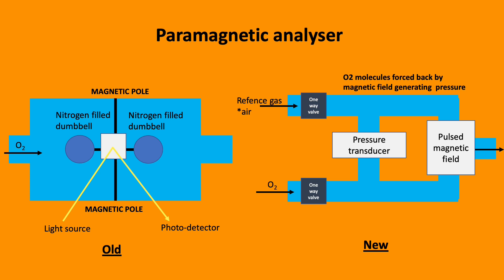Modern paramagnetic analyzers contain a sample and reference tube. Oxygen is attracted to the magnet which cycles on and off, and this pressure is detected by a pressure transducer. The higher the oxygen, the greater the attraction and the higher the pressure.